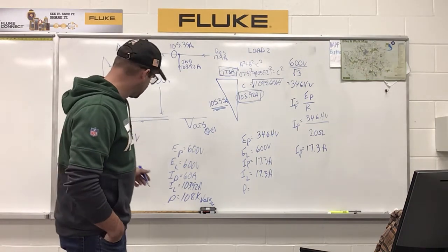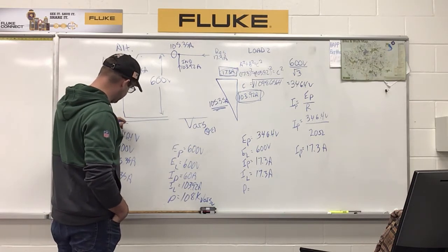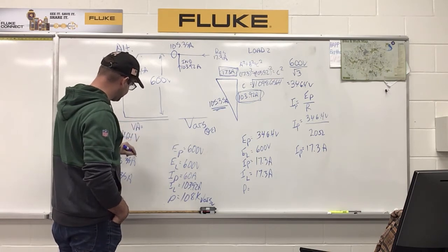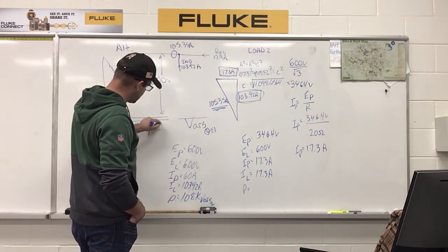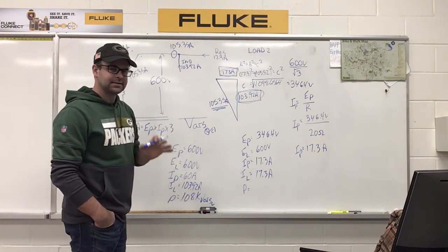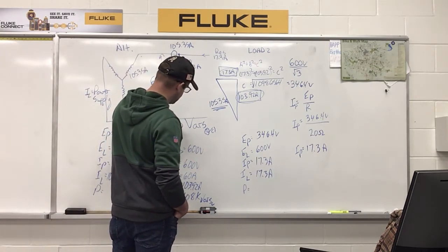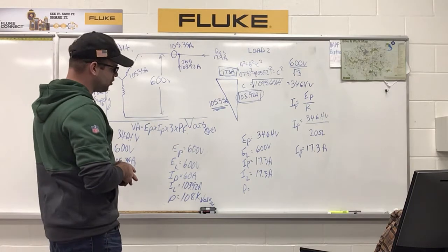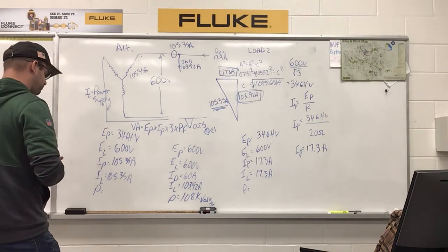So let's just calculate this out using the formula. And remember the formula, well in this case, for three-phase power, our volt amps is going to be E phase times I phase times 3, and then technically in this case we are also going to look at the power factor. Anytime you have an inductive portion to it, you also need to look at what your power factor is going to be.